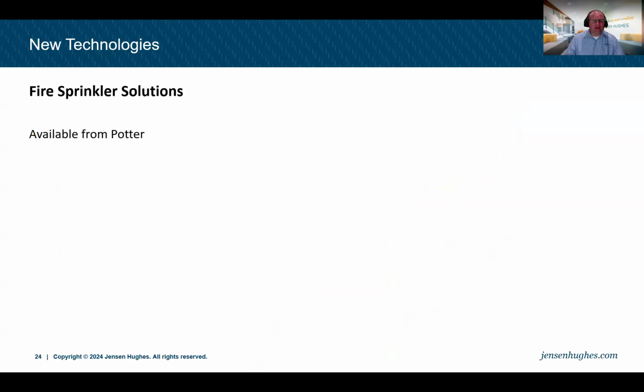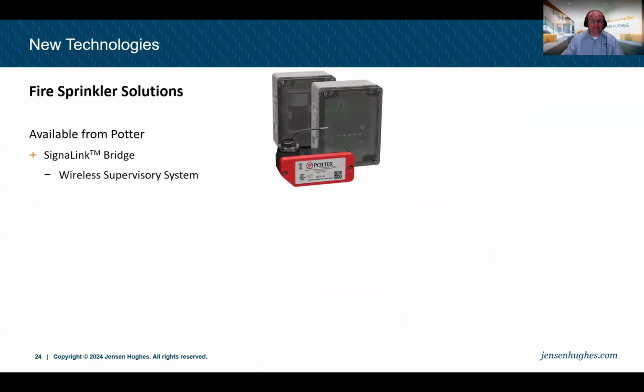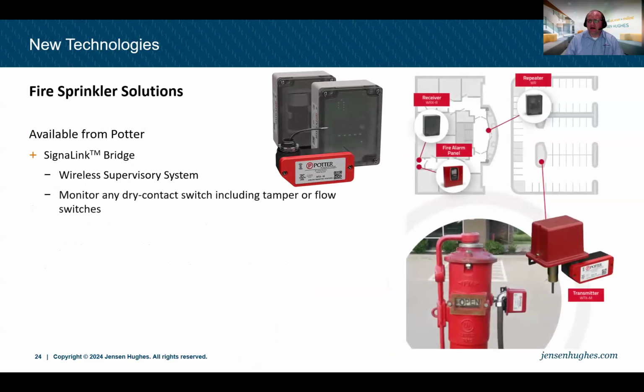And finally, also available from Potter is a technology for exterior pieces of fire sprinkler equipment, particularly an exterior post indicator valve, known as a PIV, like you see in the bottom picture there. Often these PIVs are located outside of the facility, maybe on the corner or out in the outside of the facility. We need to monitor these devices, but the only way to do it previously was to trench wiring back underneath, let's say, the sidewalk or the parking lot and get it back into the building.